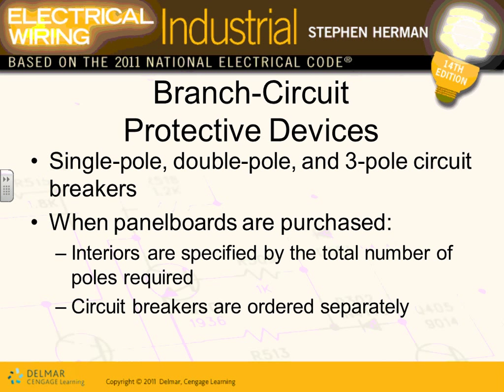Circuit breakers, guys, panels are supposed to house circuit breakers. Circuit breakers can be single pole, double pole, three pole. Everybody understand? If I have a 208 single phase, how many poles do I need? Two. If I have 120, how many poles do I need? One. If I have 208 three phase, three pole circuit breakers. So that's basically what this is telling you.